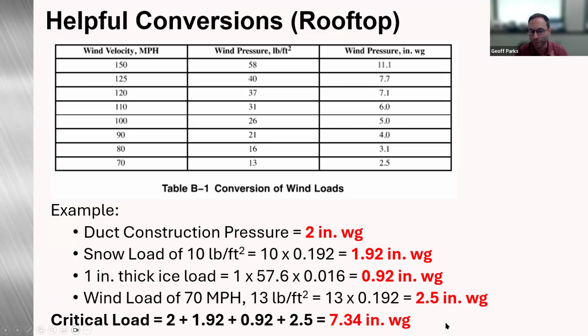So essentially, you can build out of the HVAC duct construction standards with snow loads, ice loads, and wind loads. So for this one, instead of just building a 2-inch water gauge, we would be looking at building 10-inch water gauge, essentially, because there's no 8-inch water gauge. So this is just a way to stay within the duct construction standards and stay out of the industrial. Now, if you have anything that exceeds 10-inch water gauge, then we would be looking into the industrial. Hopefully that made sense. If not, yell out.